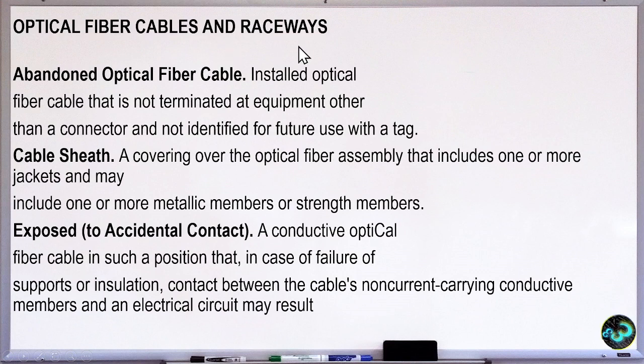So optical fiber cables and raceways. So we have abandoned optical fiber cable, installed optical cable that is not terminated at equipment other than a connector and not identified for future use with a tag. So for the word itself, abandoned, no? It is not necessarily may gamit, but it is installed, but it's not terminated in any connector or any box. Cable sheath, no? Same to sa PEC Part 2 na definition. So that is a covering over the optical fiber assembly that includes one or more jackets and may include one or more metallic members or strength members.